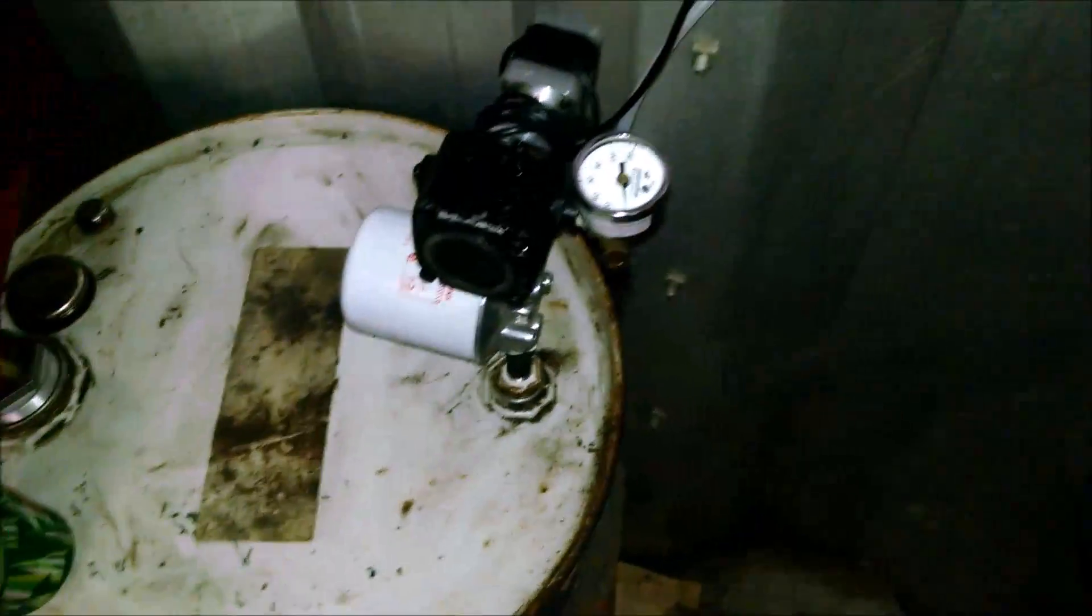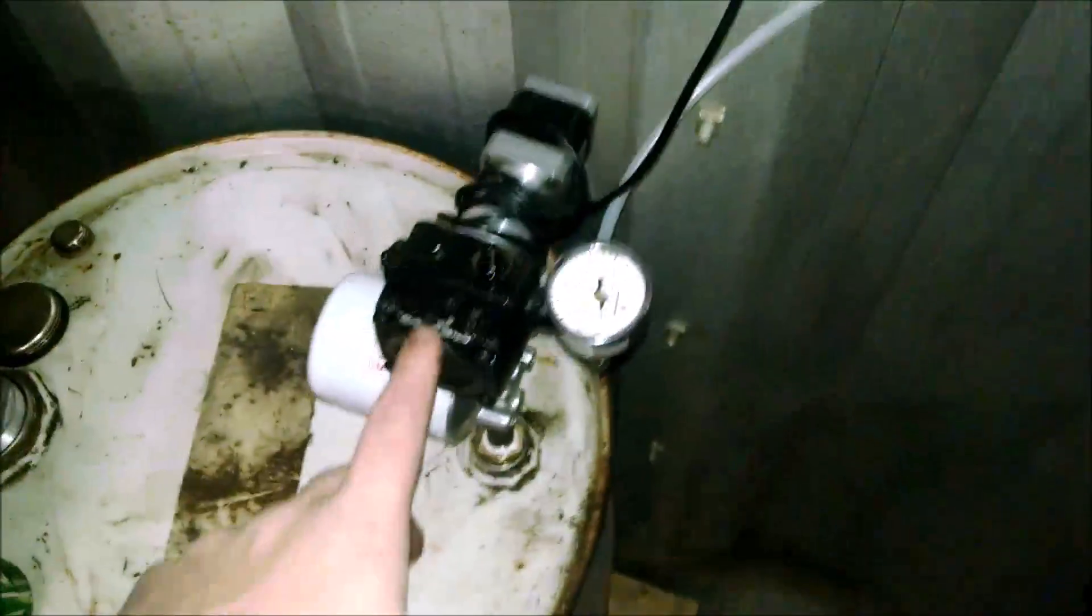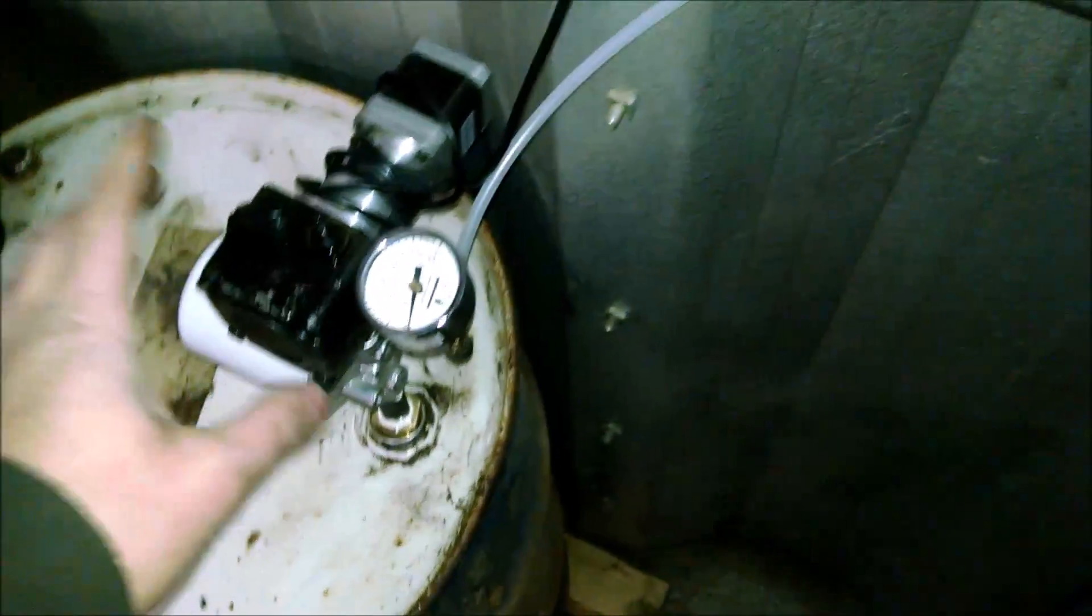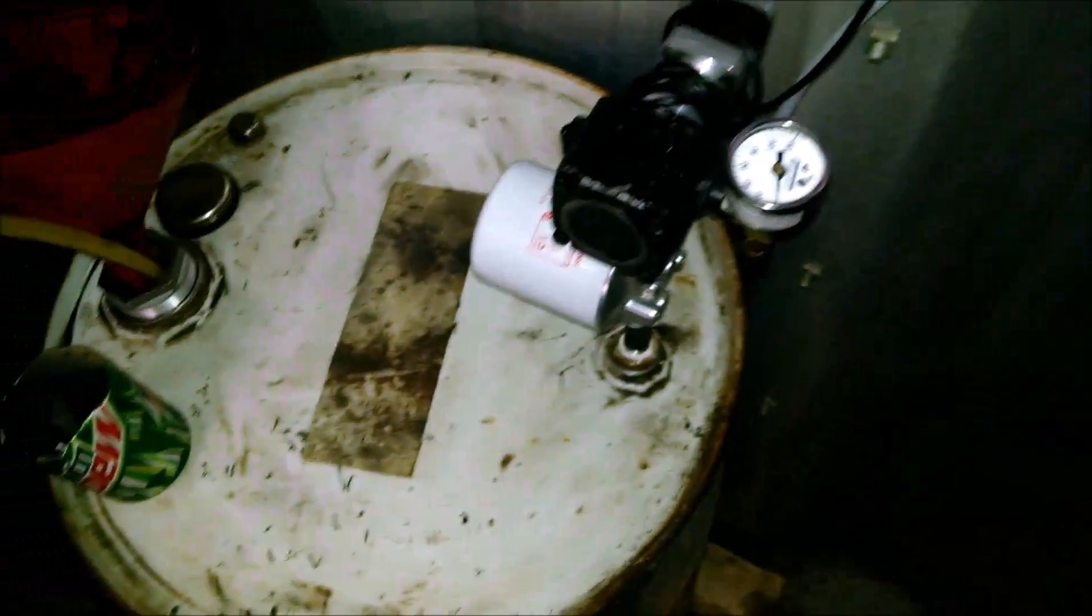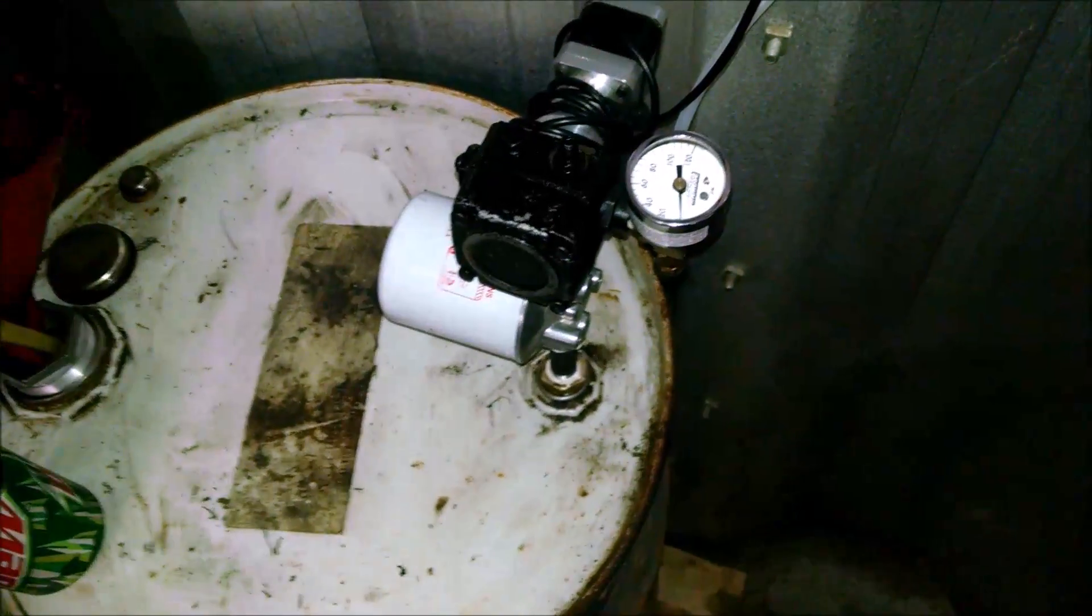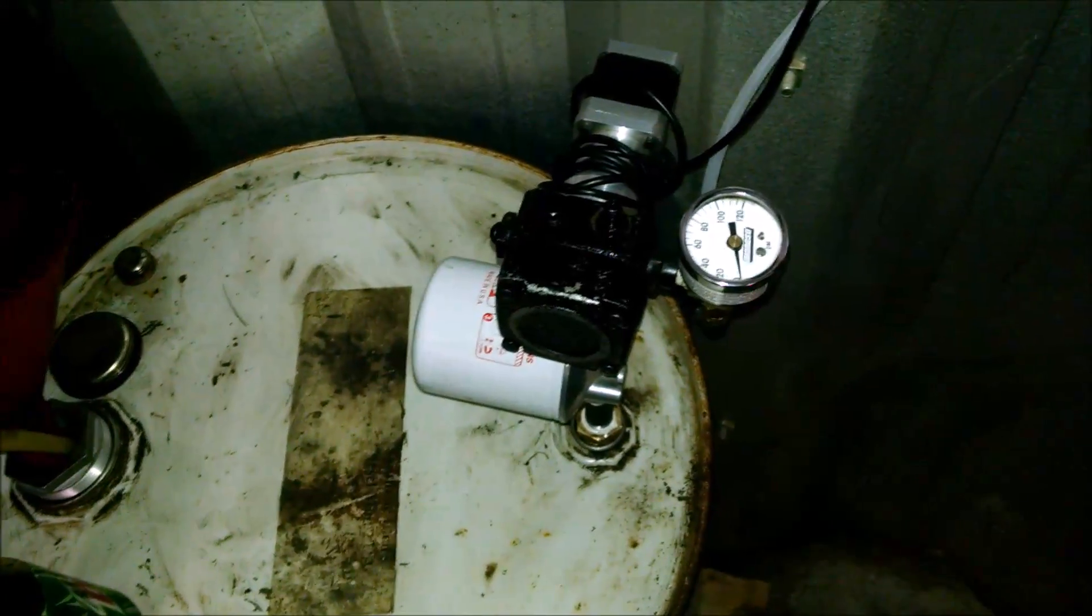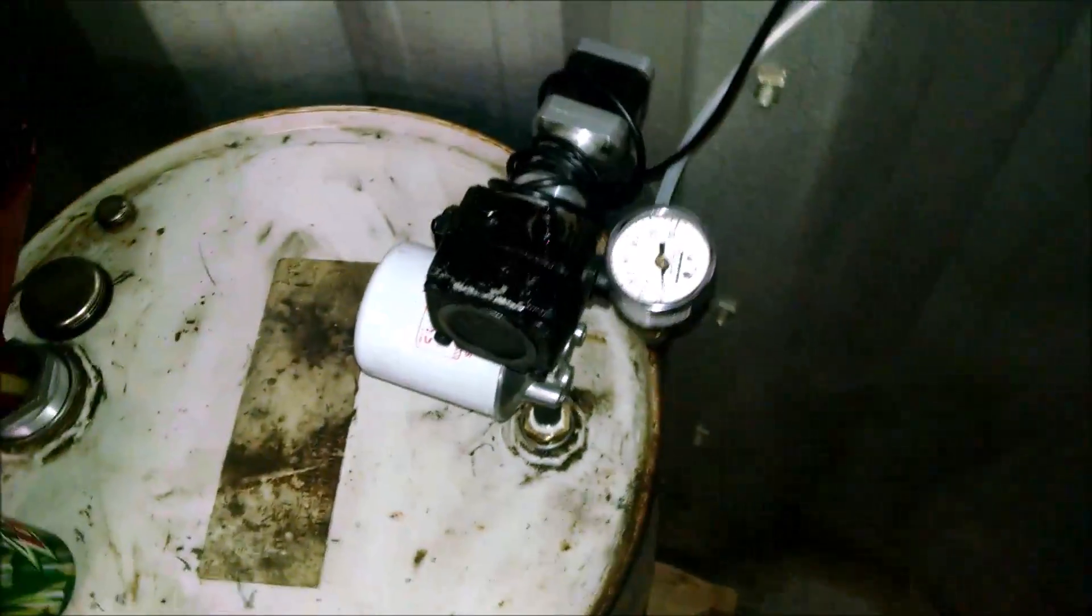What I've got is a setup, it's just a 30 gallon barrel. And this is actually a pump for a heating oil system. Now the difference is that this typically runs about 100 to 120 psi, and the purpose being that they actually atomize the oil out of those nozzles with pure pressure. They don't use air to assist it. In this case, all I'm using it for is to draw oil from the tank and bring it over to the nozzle at a pressure of anywhere from about 3 to 12 psi, depending on how cold it is.